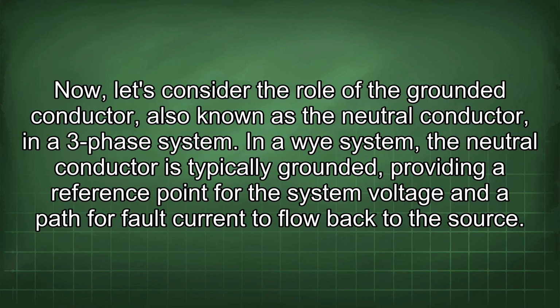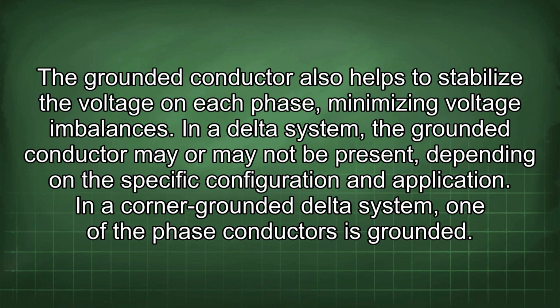Now let's consider the role of the grounded conductor, also known as the neutral conductor, in a three-phase system. In a Y system, the neutral conductor is typically grounded, providing a reference point for the system voltage and a path for fault current to flow back to the source. The grounded conductor also helps to stabilize the voltage on each phase, minimizing voltage imbalances. In a Delta system, the grounded conductor may or may not be present depending on the specific configuration and application.